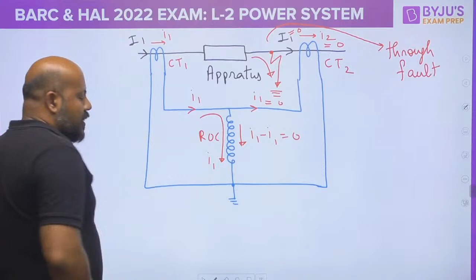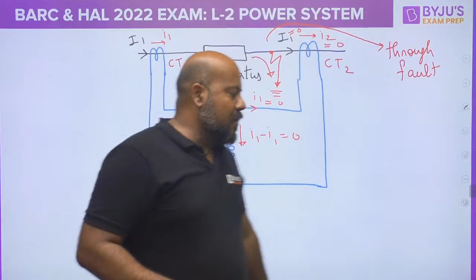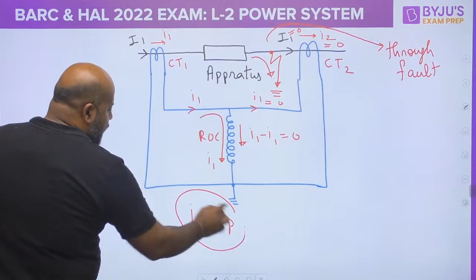There is no fault. Now let us try to understand a case when the fault is present in the system. Suppose, because of any reason, some fault occurs here in between these two current transformers, and such a fault we call a through fault, or you can say a fault inside the system which is being protected. If you get the fault, then this relay is going to operate.